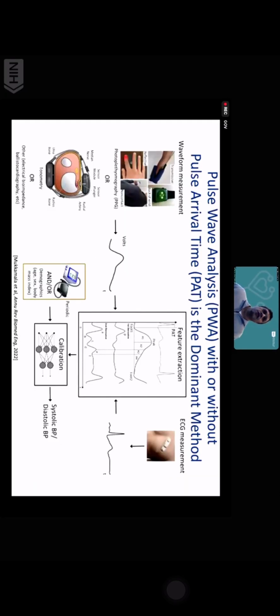Next, please. So most of the studies, and likely all of the regulatory cleared devices, employ pulse wave analysis with or without pulse arrival time. So pulse wave analysis methods typically measure a photoplethysmography or PPG waveform, which indicates small vessel blood volume oscillations, or a tonometry waveform, which indicates net peripheral artery forces. So neither waveform directly indicates blood pressure. So these methods will then extract features from the waveform and map or calibrate these features to blood pressure values using machine learning. Pulse wave analysis with pulse arrival time methods also record an ECG waveform to extract pulse arrival time as the time delay between the ECG and hemodynamic waveforms, and possibly other features.